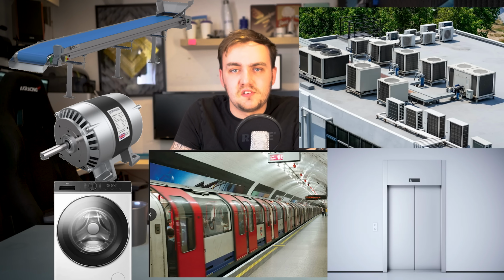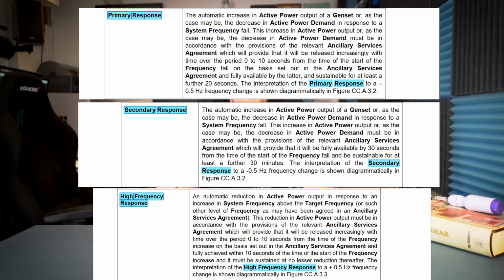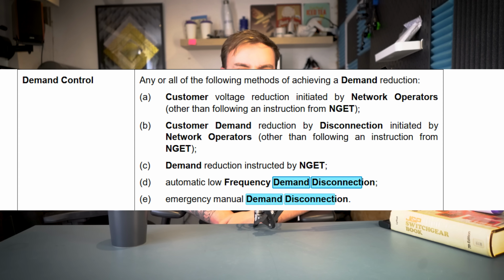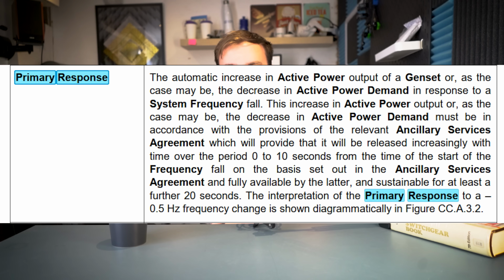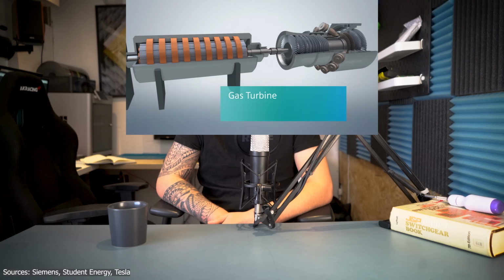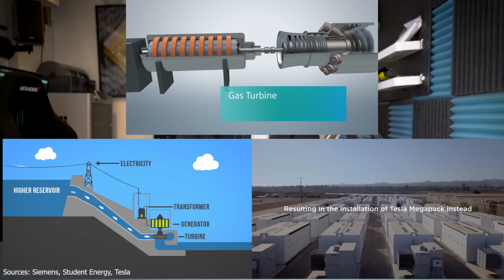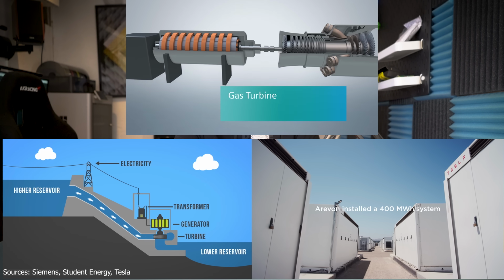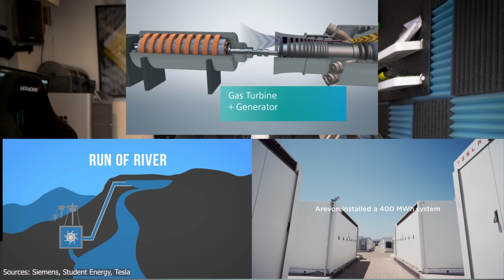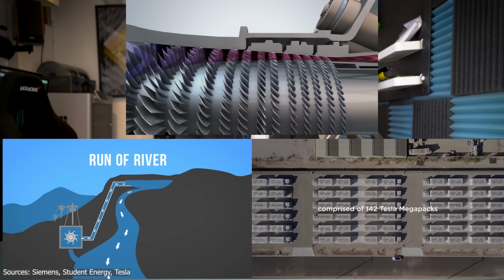Frequency is super important because a lot of machines and electronics rely on a stable 50 Hz signal, as it's what they were designed for, and straying too far from that can quickly damage them. To manage all of this, the NESO keeps different types of reserves ready to go, like backup power and load reduction tools. These reserves come in several layers depending on how quickly they need to act. First, there's primary frequency response, which kicks in within seconds. This uses fast acting generation like gas turbines, hydropower and increasingly batteries, which can inject power almost instantly. Some wind farms can also help by ramping up curtailed generation if needed.